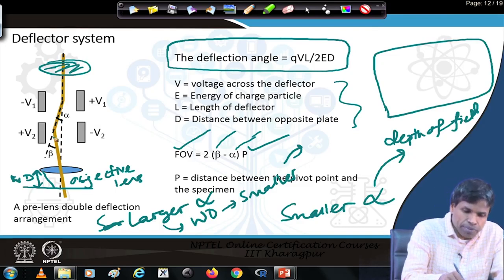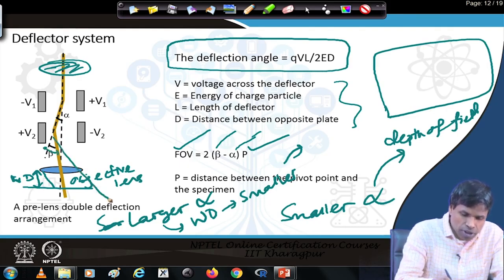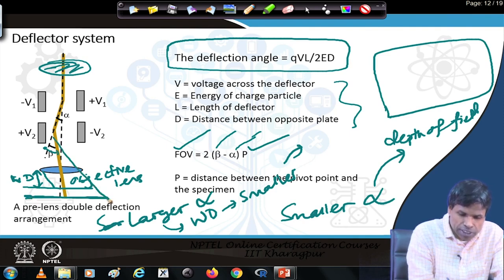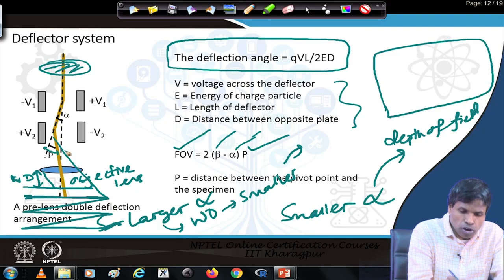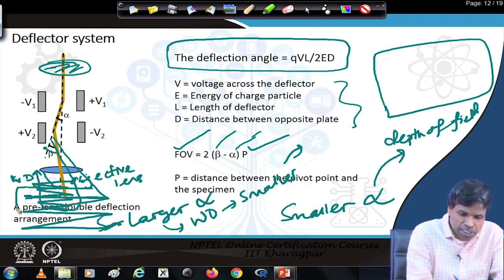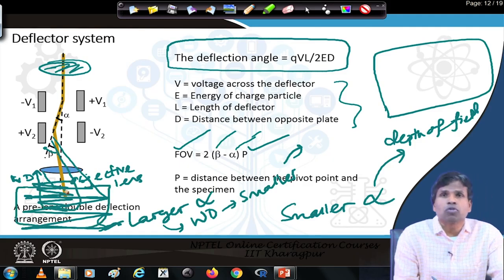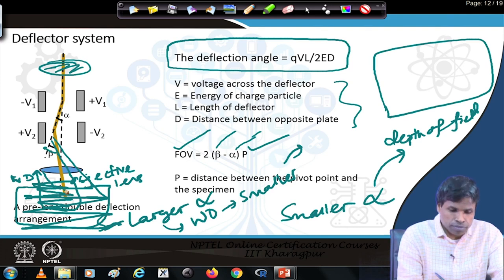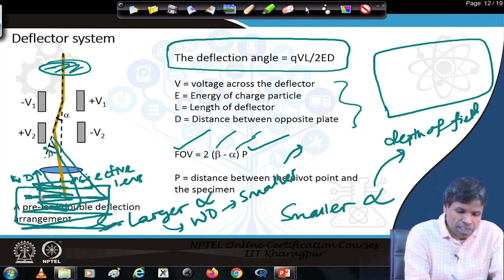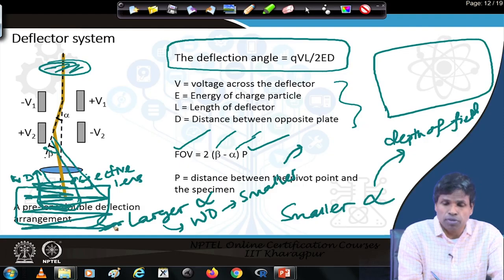So depending on requirements, the deflector system can be placed before or after the objective lens. By choosing the deflection angles alpha and beta, we can scan over a larger area or a smaller area. If we are scanning over a smaller area, magnification will be higher; if we are scanning over a larger area, magnification will be smaller.